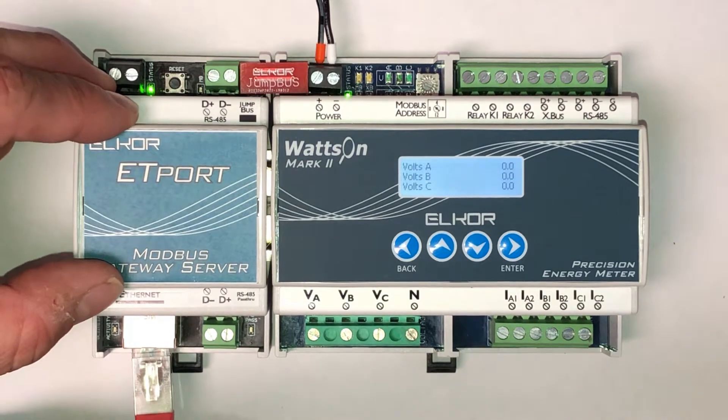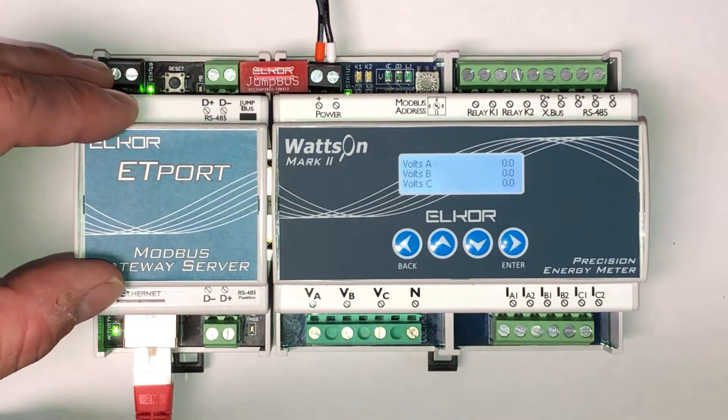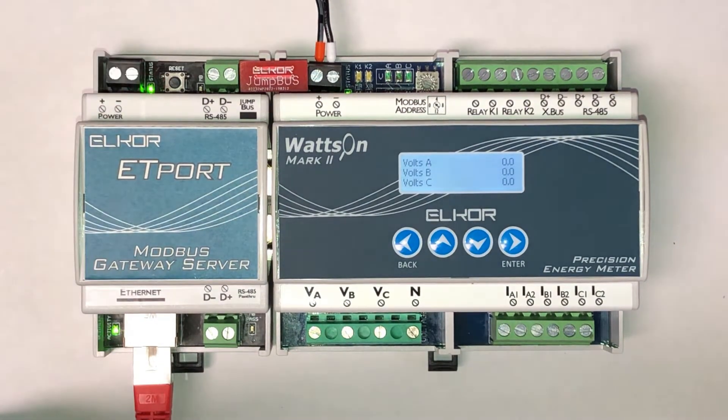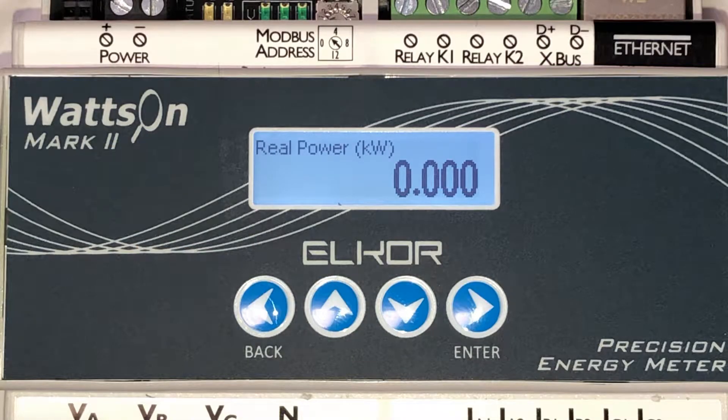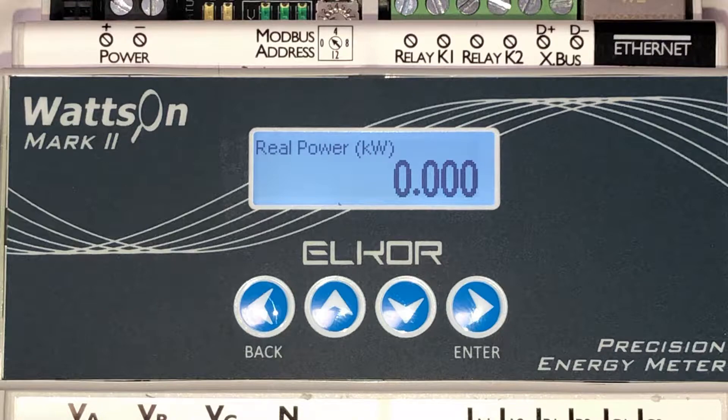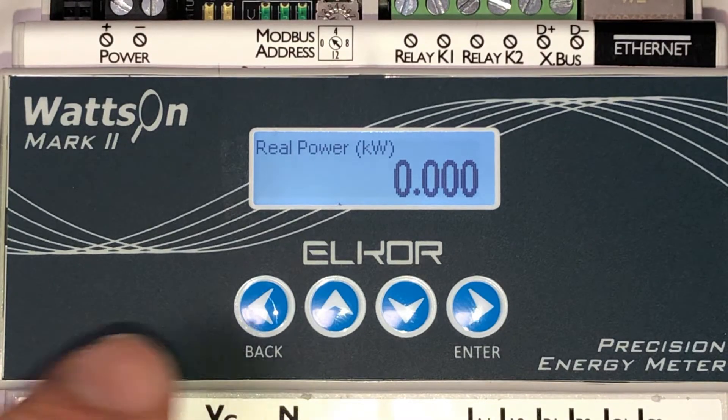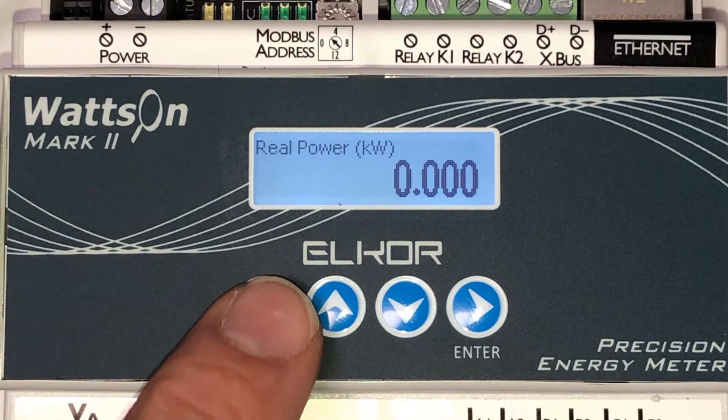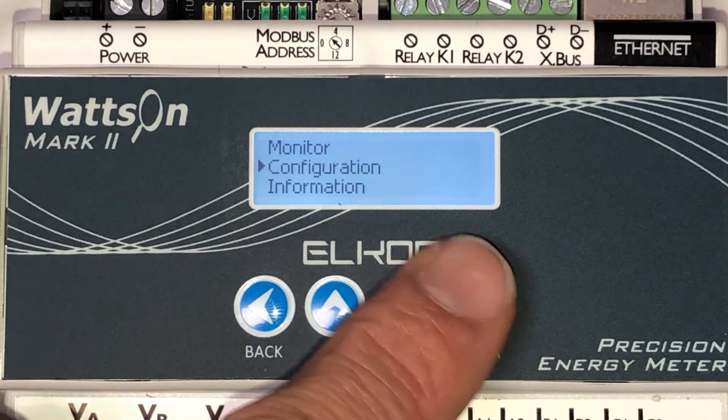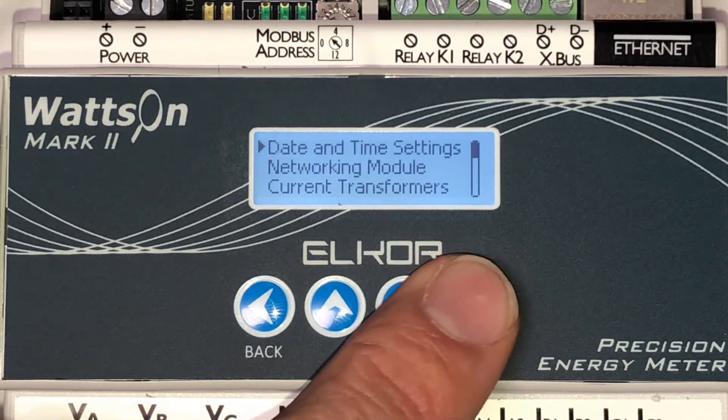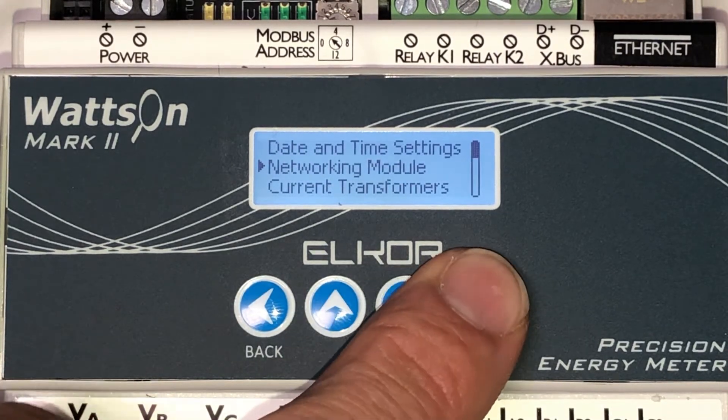Ensure to connect an Ethernet cable to the bottom of the ET port. In the case of the E4 model of the WattsOn Mark II with the onboard display, it is possible to view the configured network parameters on the LCD. To do this, press the back button to enter the configuration menu, select Configuration and then select Networking module.